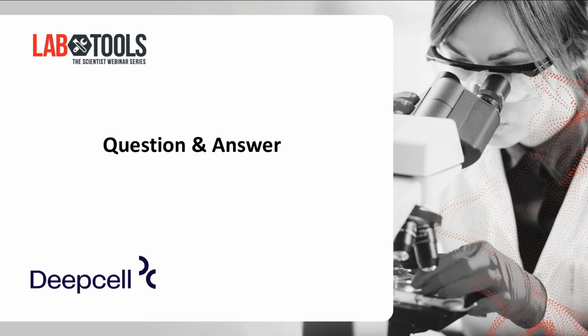You might even be able to take the image of them and do some manual analysis on it or in some imaging software, but it's pretty low throughput. Flow cytometry has the value of being extremely high throughput, but often relies on labels, and doesn't necessarily have the high dimensionality of the AI that we have. And then, depending on the tool you're using, if you want to actually keep those cells viable and sort them and do additional analyses on them, that's really where the REM-I shines, right? It's able to bring all those three things together into one platform and then also provide that sorting.